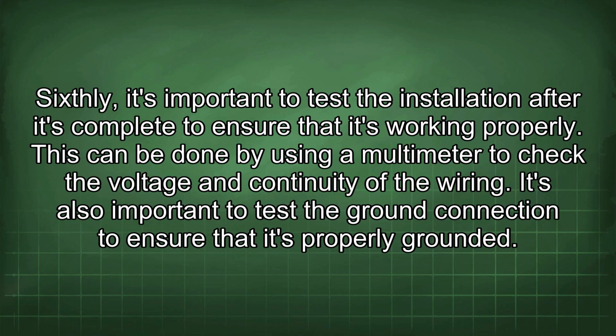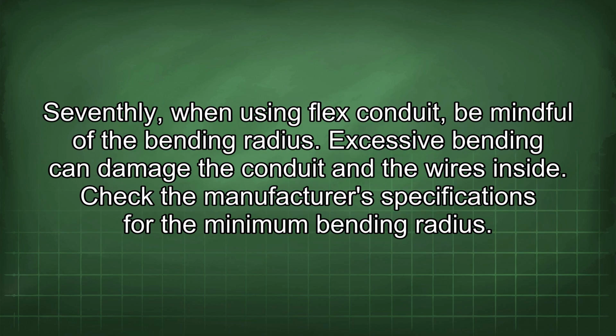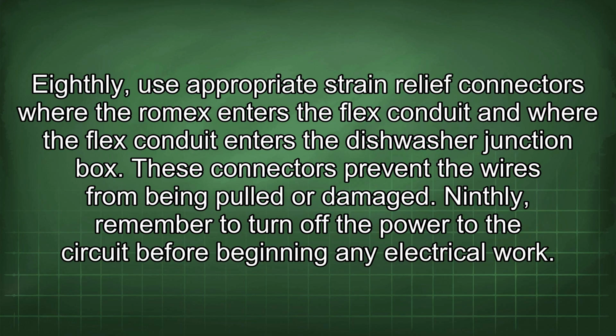Sixthly, it's important to test the installation after it's complete to ensure that it's working properly. This can be done by using a multimeter to check the voltage and continuity of the wiring. It's also important to test the ground connection to ensure that it's properly grounded. Seventhly, when using flex conduit, be mindful of the bending radius. Excessive bending can damage the conduit and the wires inside. Check the manufacturer's specifications for the minimum bending radius. Eighthly, use appropriate strain relief connectors where the Romex enters the flex conduit and where the flex conduit enters the dishwasher junction box. These connectors prevent the wires from being pulled or damaged.